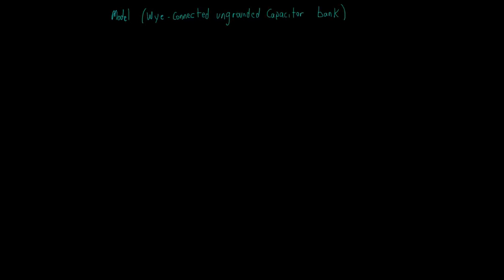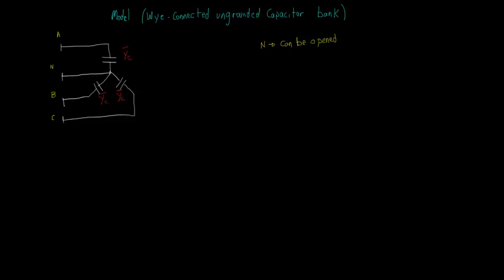Now, let's analyze the model of a Y-ungrounded capacitor bank. In this case, we have nodes A, B, C, and the neutral, which can either be connected to another conductor, for example the neutral conductor of a line, or be left open. The voltage at the center node is not zero anymore; we will name it as Vn. Then, the voltage across the branch connected to phase A, for example, will be Van. There are four injected currents: Ia, Ib, Ic, and In.